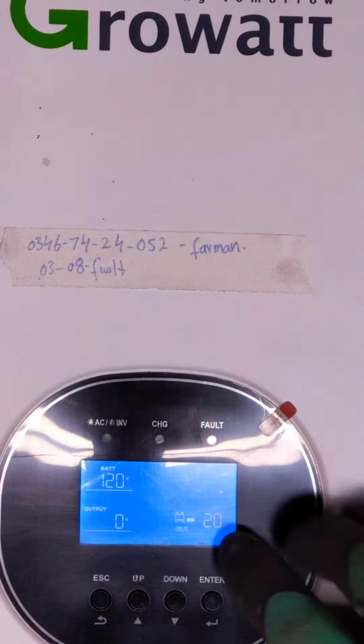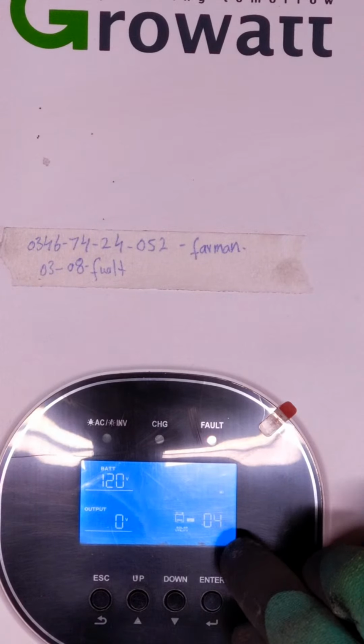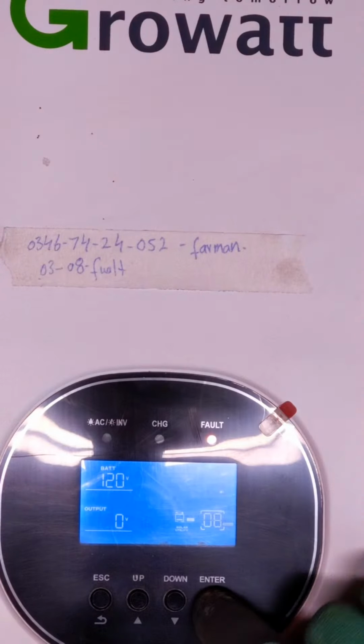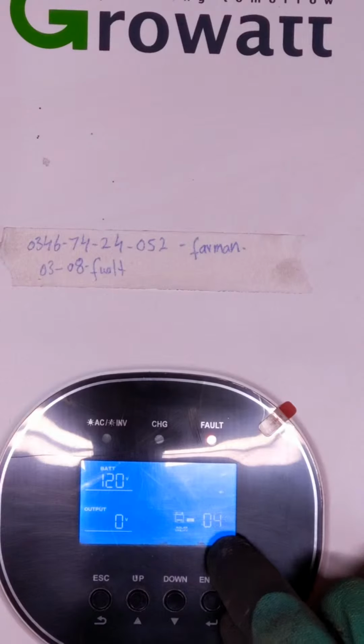First we need to set on user define, because here we have lithium, and I have a lithium bank and everything, but we have faults in this inverter. As you can hear, fault 08, and fault 20 is just for communication, and we have fault 03.